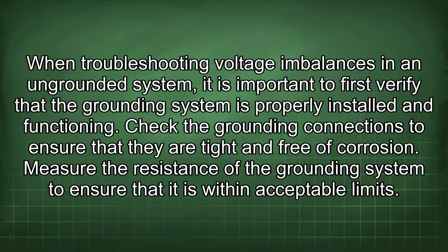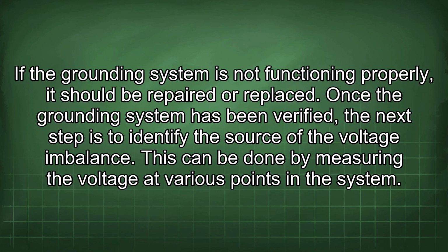application. When troubleshooting voltage imbalances in an ungrounded system, it is important to first verify that the grounding system is properly installed and functioning. Check the grounding connections to ensure that they are tight and free of corrosion. Measure the resistance of the grounding system to ensure that it is within acceptable limits. If the grounding system is not functioning properly, it should be repaired or replaced.